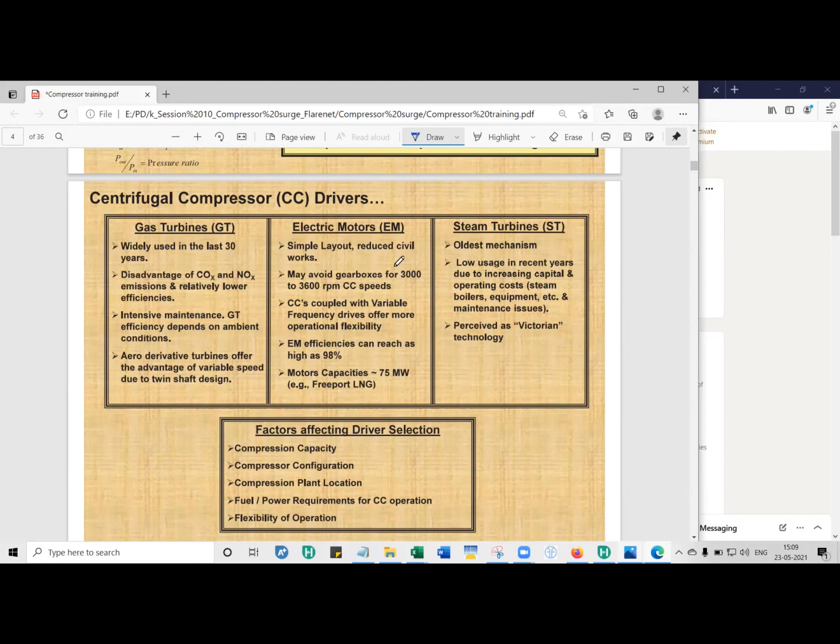Let's say it's 50 Hertz and 2-pole motor. 120 into 50 by 2 comes to 3000 RPM. The US is the only country which uses 60 Hertz. 120 into 60 by 2 gives you 3600 RPM. But does this mean that the gas compressor can run only at 3000 RPM? No, you can run it at higher speeds by using a gearbox.